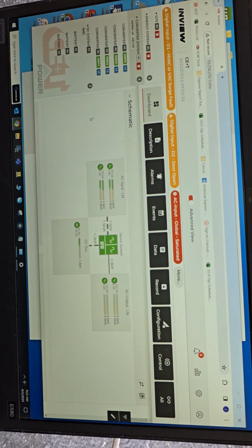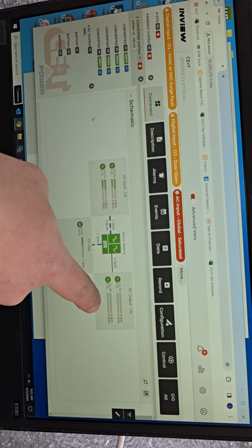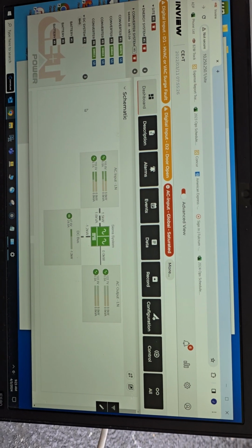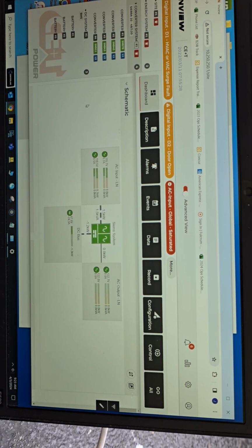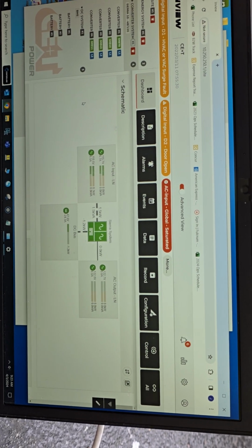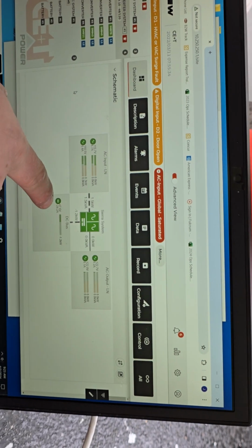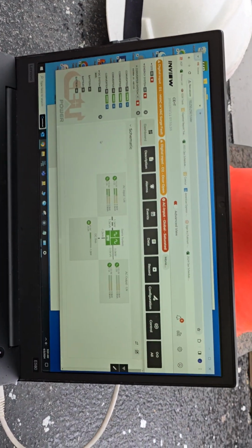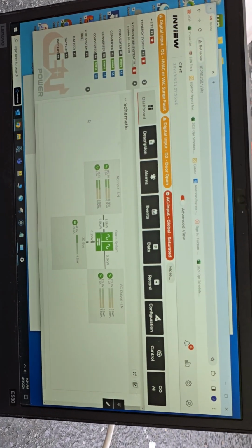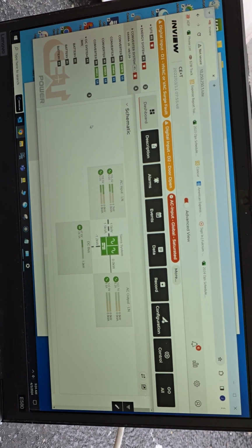So when you come back to dashboard, this is where you're gonna see the actual voltage and pull. So this should be like 120, 120, 120, 120. And then when he turns this on, obviously the amperage is going to go up. And then you try to balance it. It should already be balanced, yeah, based on the settings that we have. Is he turning it on now? Yeah, you can turn the rest of it up once you check. He's just checking voltage to make sure our neutral's not floating. Yeah. Better not be floating.